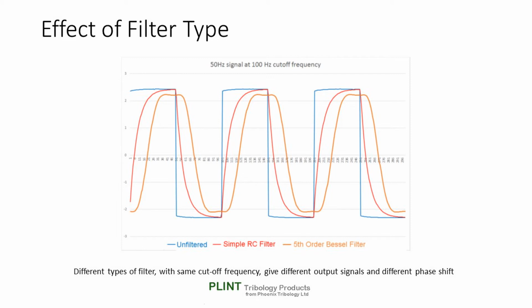It would perhaps be an omission to conclude this section on filtering and signal bandwidth without stating a preference for a particular type of filter for reciprocating tribometer applications. The best filter for time domain applications is a Bessel filter, a type of filter frequently used for cleaning up digital signals, which are perhaps a good analogue for a dry or boundary lubricated friction signal. It provides minimum distortion of rapid slope changes, a uniform group delay, and the lowest wideband noise. A Bessel filter is less well suited to frequency domain applications as it has a drooping amplitude response and a gentler cutoff frequency than other filter types.